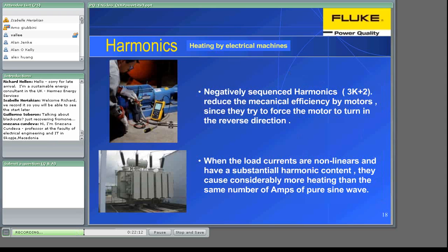Transformers are affected in two ways by harmonics. Firstly, the eddy current losses, normally about 10% of the loss at full load, increase with the square of the harmonic order. This results in a much higher operating temperature and a shorter life. The second effect concerns the triple harmonics. When reflected back to a delta winding, they remain circulating in the primary. This results in a higher temperature and saturation. Equipment such as a transformer is usually expected to last for 30-40 years. Now, having to replace it in 7-10 years, you can imagine the serious financial consequences.